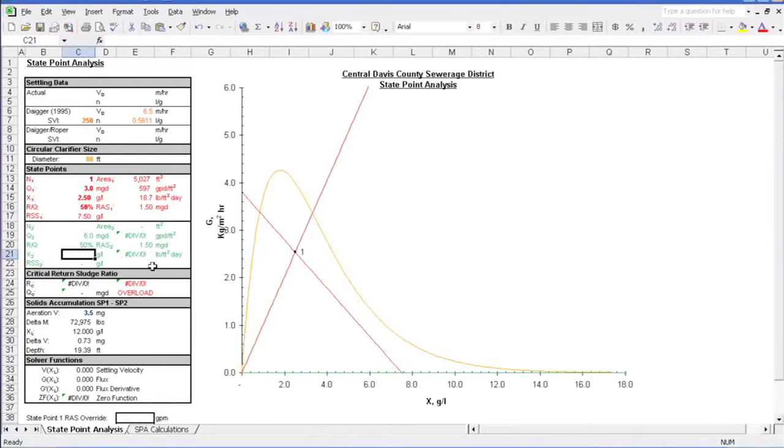So it's a rainstorm. Hits your system and the flows begin to rise. Before you know it, your influent flow has risen to 4MGD and your RAS pumps don't automatically adjust with the flow. For this, we need to override the RAS rate.